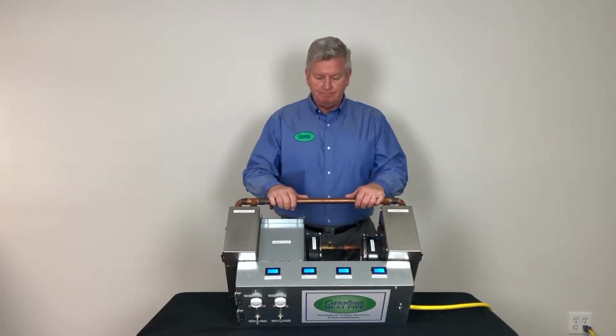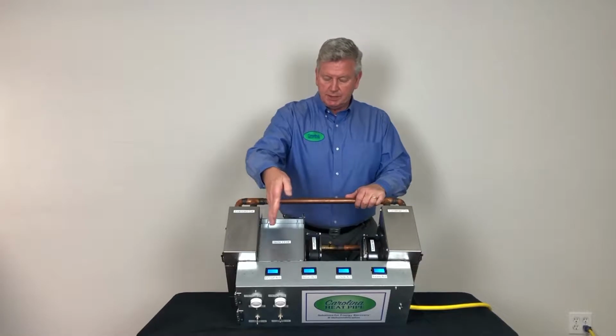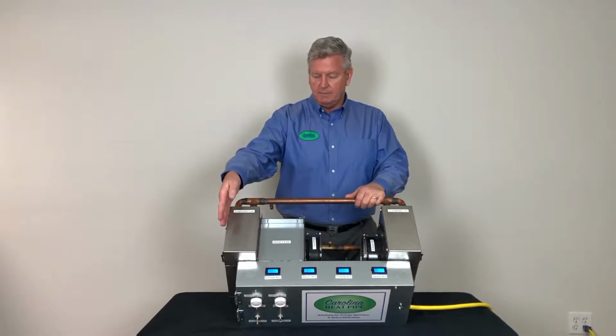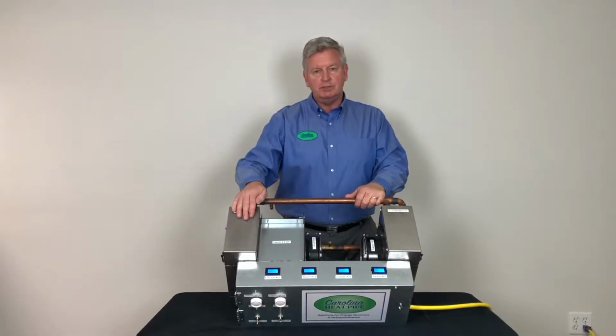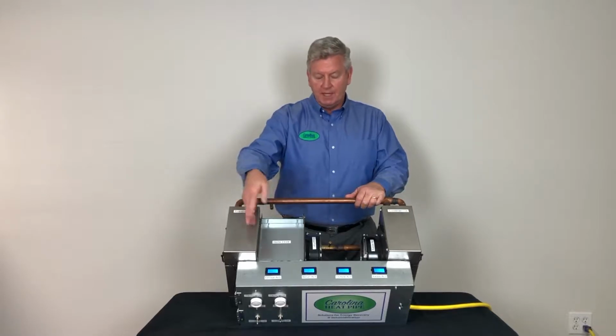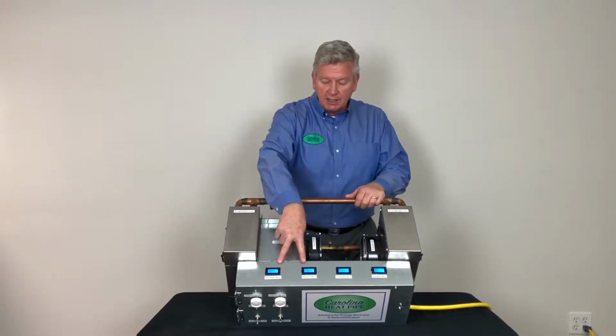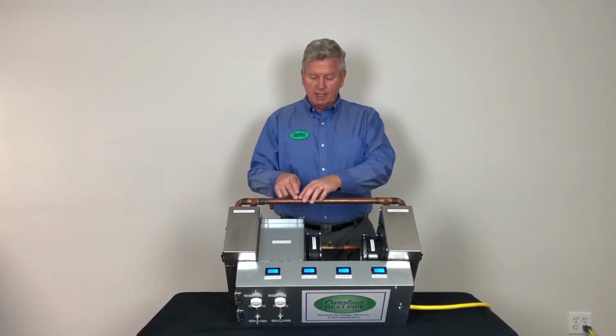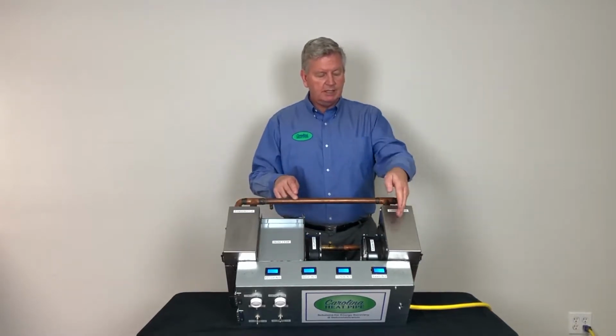Here are the temperatures. The return air temperature is between the electric heater and the exhaust coil, and the exhaust air is after the exhaust coil. The difference between the two temperatures is the amount of heat energy picked up by the exhaust coil. In this case, approximately 15 degrees. This heat energy is then transferred along the vapor line to the condenser coil.